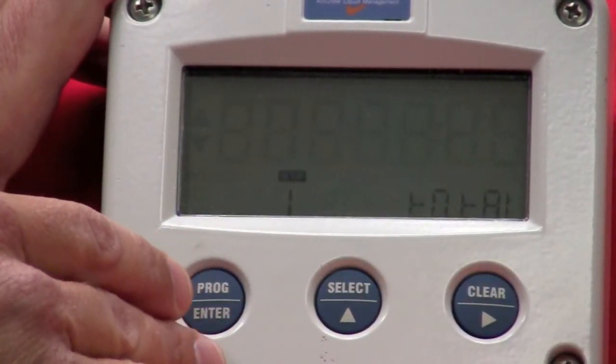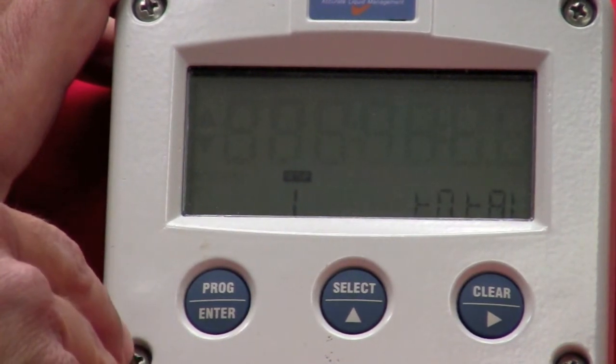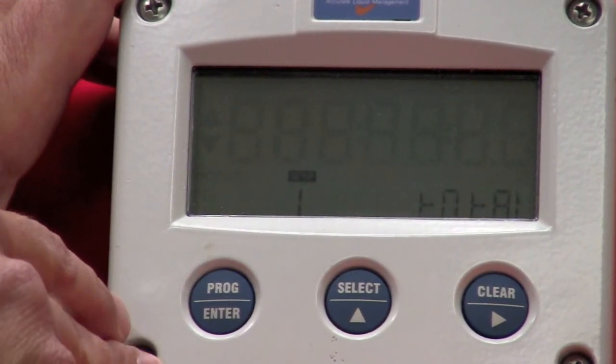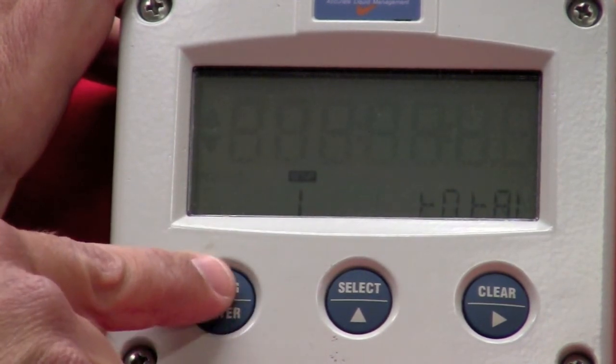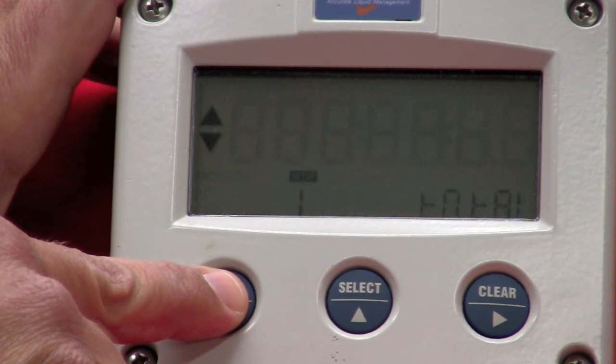To jump out of programming, there's two ways to do it. One is to let the unit time out, which takes two minutes before it will go back to the run mode. Or a quicker way is just hold in your programming key for two seconds, and it will return back to the run mode.